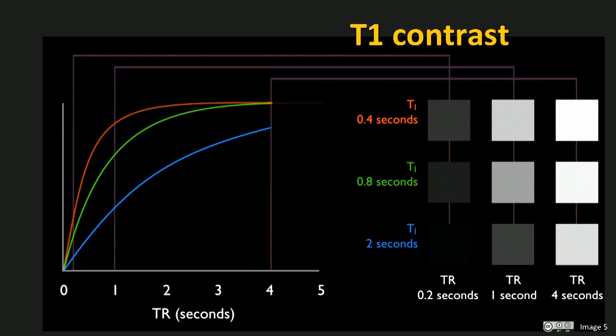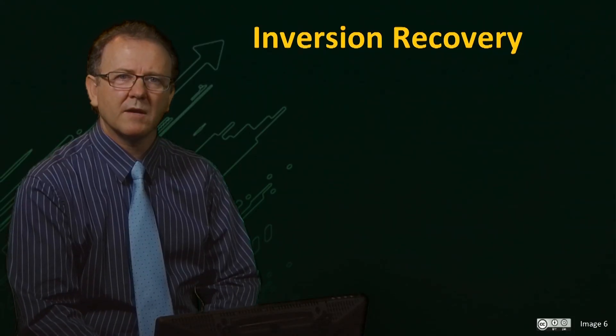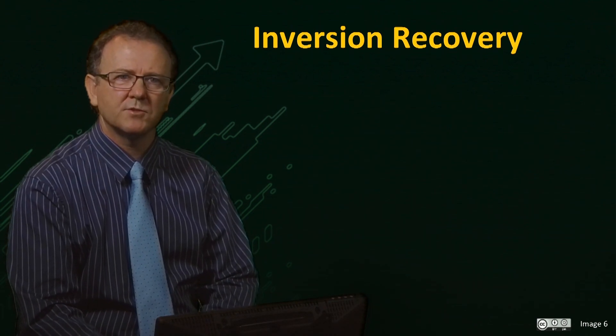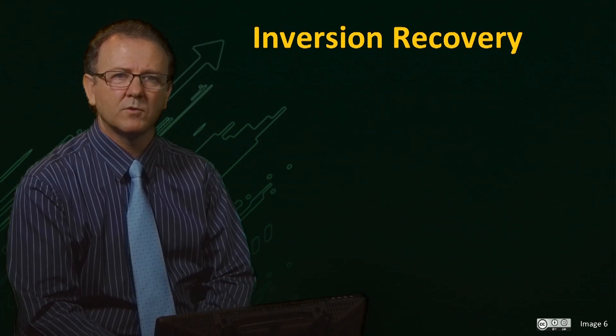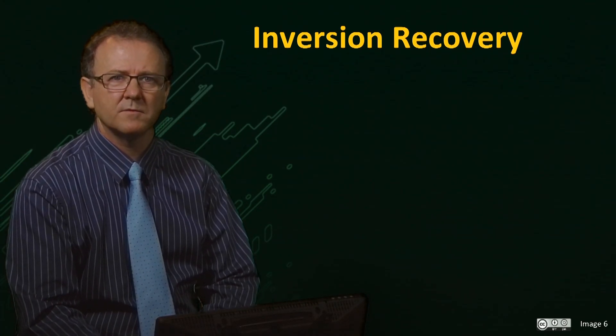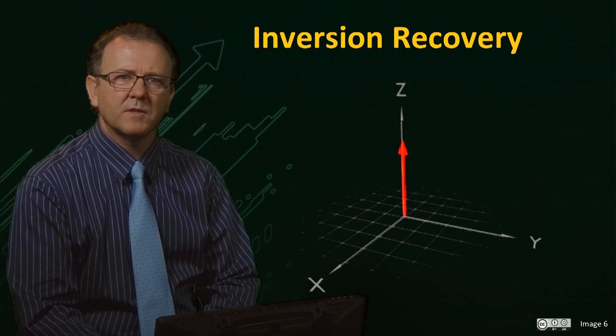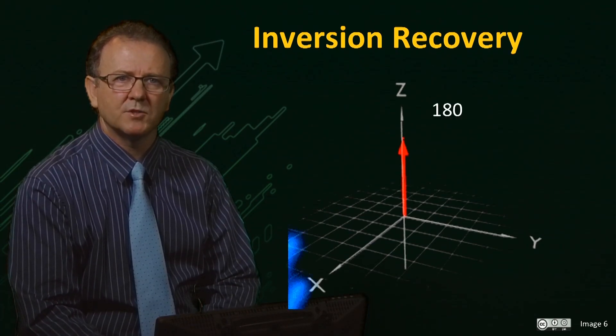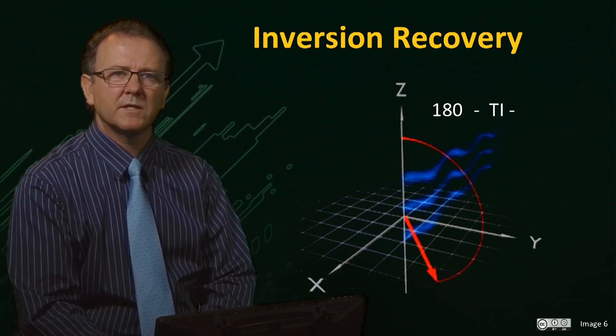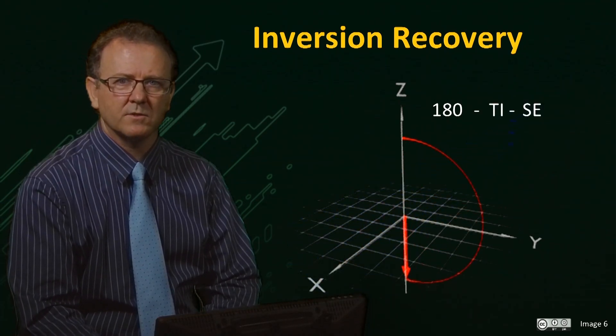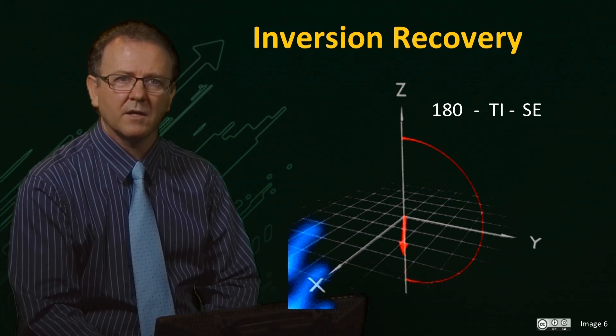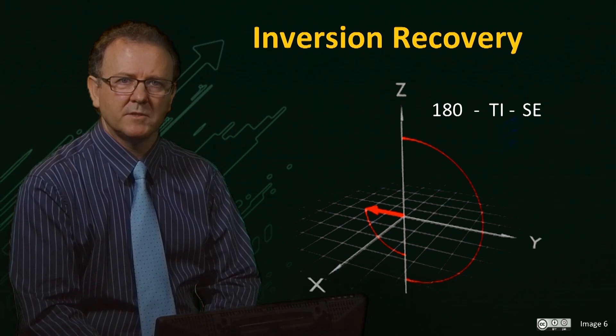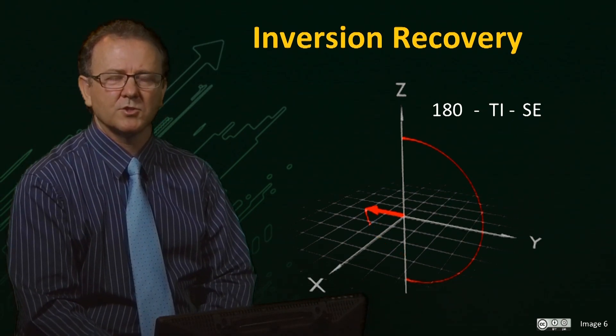The inversion recovery T1 sequence allows us to improve the contrast between tissues and selectively suppress the signal for tissues of a particular T1 value. To remind you of the inversion recovery experiment, a 180 degree inversion pulse is applied to the spins, then we wait a time for T1 relaxation to occur, here called TI for inversion time. And then the spin echo imaging sequence is applied to image the available longitudinal magnetization.